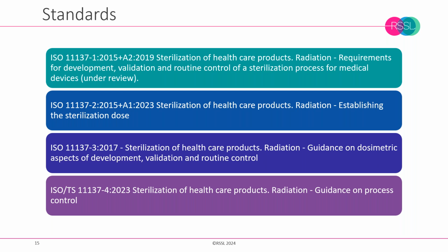Part 1 covers the development, validation, and routine control of the radiation sterilization process. Part 2 is about the specific methods for determining the minimum dose needed to achieve the specified requirement for sterility. Part 2 also looks at the sterilization dose audit, which is used to demonstrate the continued effectiveness after the validation has been completed, to ensure that we have consistency of sterilization. Part 3 is guidance on the way we're measuring the effectiveness of radiation through dosimetry. And part 4 is about ongoing controls.